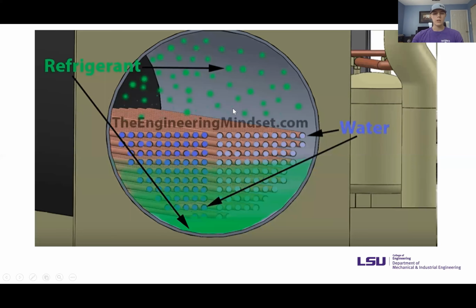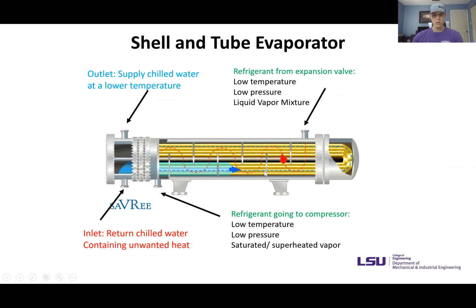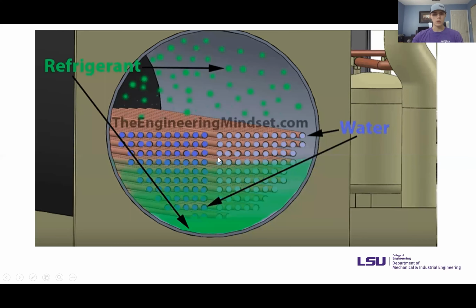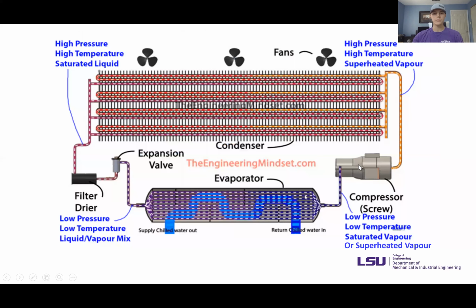Here we can see the internal components of the evaporator. So you'd have the refrigerant that flows freely through the evaporator, and the water, as shown previously, the water flows through small tubes inside the evaporator. This is a closed system, so the refrigerant and water never make contact with each other. The refrigerant just picks up the unwanted heat from the chilled water.